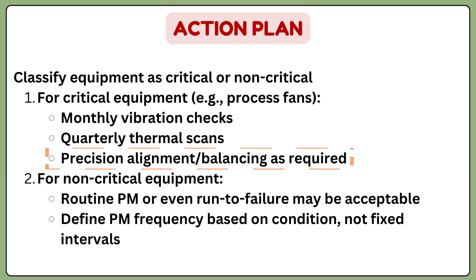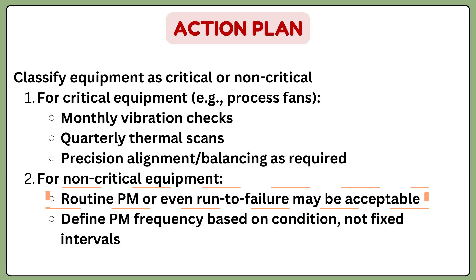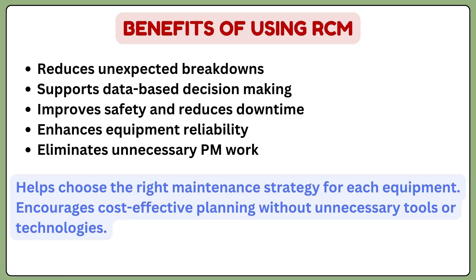What we now have is a smarter plan instead of simply running the fan to failure or blindly following a PM schedule like overhauling every year or replacing bearings every two years. The benefits of this RCM technique are: reducing unexpected breakdowns, focusing on data-based decision making, improving safety, reducing equipment downtime, and improving fan reliability.